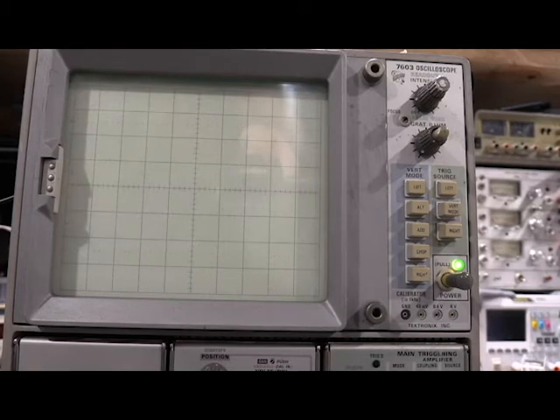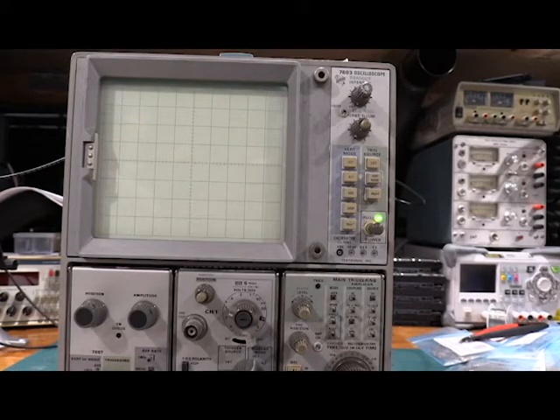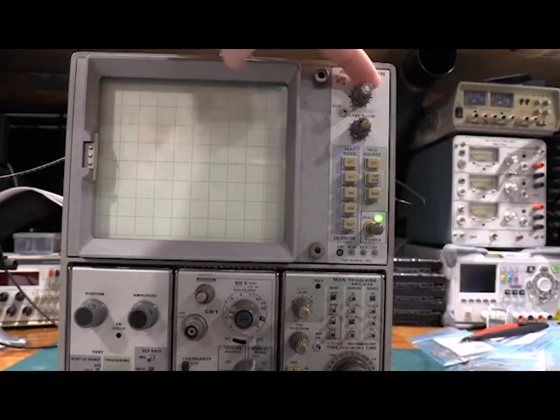Next up is checking the Z-axis DC levels. Okay, for the DC levels, there wasn't really much to show due to the fact that the trace actually should be off screen because you have to turn the intensity up to 100%, so you don't want it burning in the tube. On the Rigel scope, which is my test scope, I got a 65.2, and then when you slow down the time base, I got a 37.2, with the difference being 28 volts. The service manual says I should have between 25 and 35 volts, so that is well within spec, and everything is looking good.